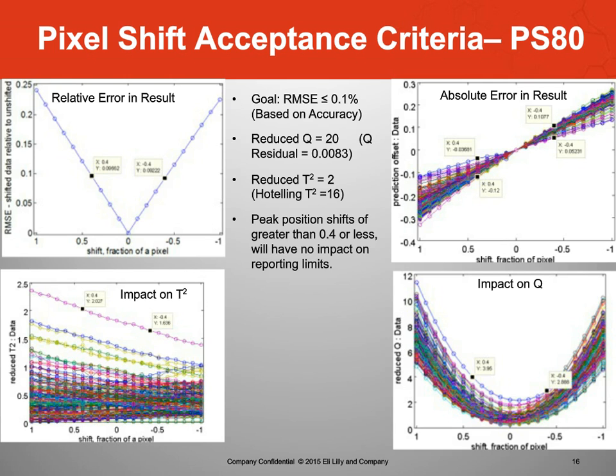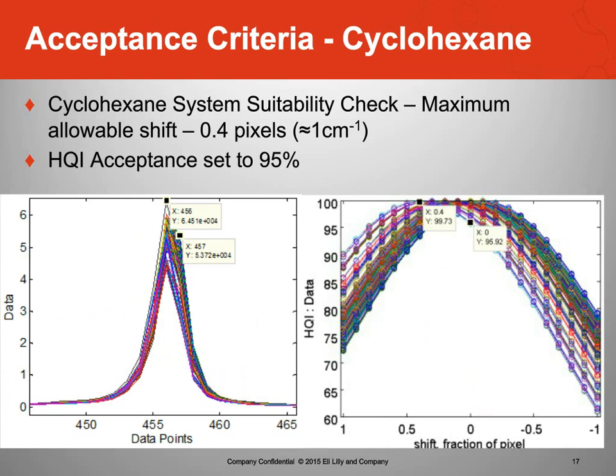So what does that mean for cyclohexane? We use HQI for our determination. The analyst comes in and runs cyclohexane as a system suitability check, to make sure the system is running properly. What would we expect for an HQI? If we look at the data, at pixel shifts of 0.4 plus or minus 0.4, the range could be anywhere between 96 and 99. I conservatively said let's just round down and go with 95% HQI. That seemed to do the trick. We've not failed to date on that HQI.